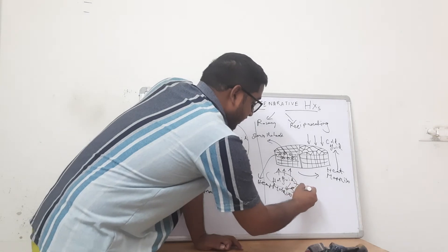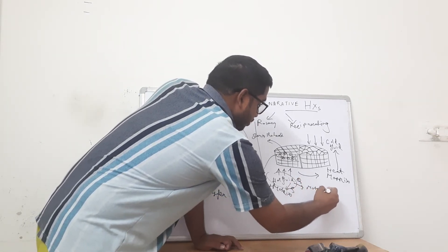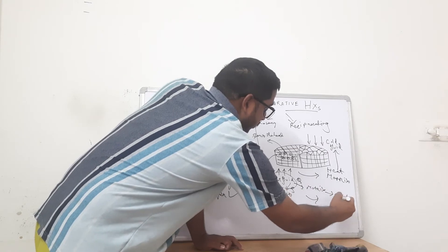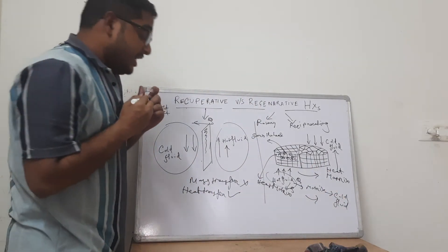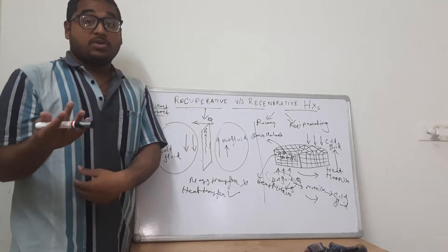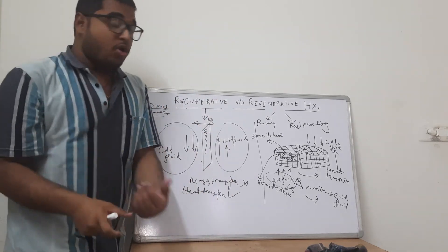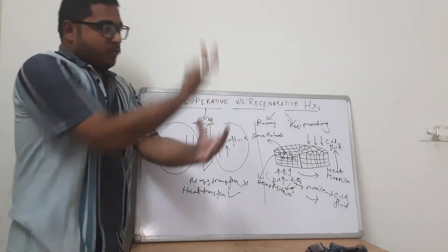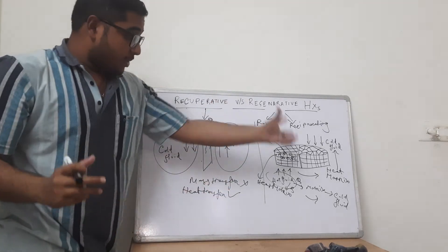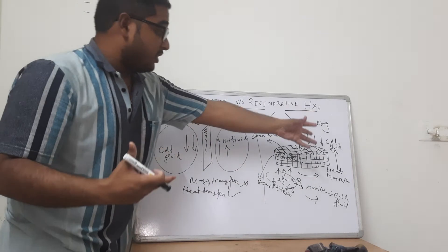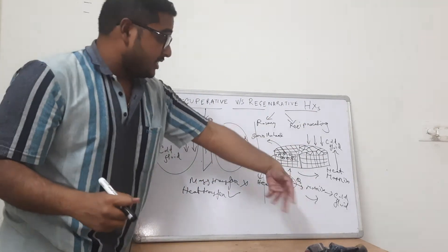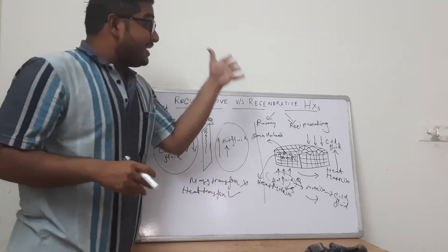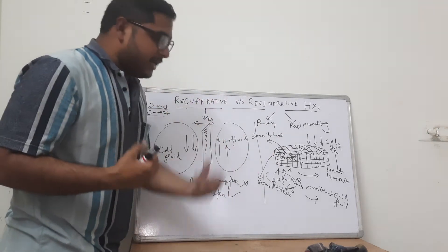So firstly, the hot fluid transfers heat to the matrix — the core structure. The matrix stores the heat within itself, rotates, and then gives this heat to the cold fluid. Partially, the heat is stored by the heat matrix and then transferred to the cold fluid. Both the hot fluid and the cold fluid pass through the same matrix structure in a continuously rotating circuit: the hot fluid comes in, gives heat to the matrix, the matrix rotates and comes in contact with the cold fluid, and the cold fluid withdraws the heat from the matrix and moves out. This is a continuous and quick procedure.